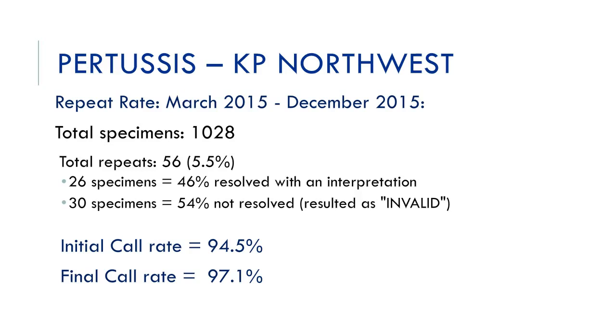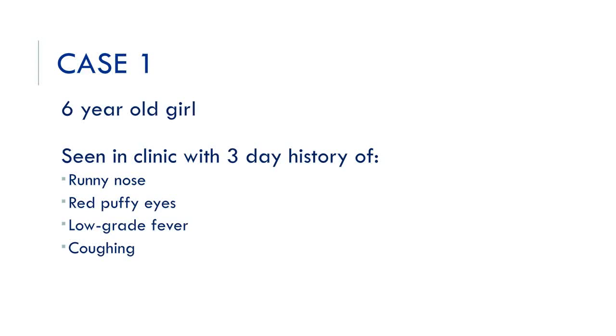Of these 1,000 samples, we had to repeat 56 of them that gave an invalid result, so we repeated about 5.5% of those samples. Of those 56 samples, 26, or 46%, resolved with an interpretation. 30 of those 56 samples, or 54%, gave us a second invalid result. So we had an initial call rate of 94.5% with a final call rate of 97%, which again we feel is very acceptable for this rapid molecular-based assay.